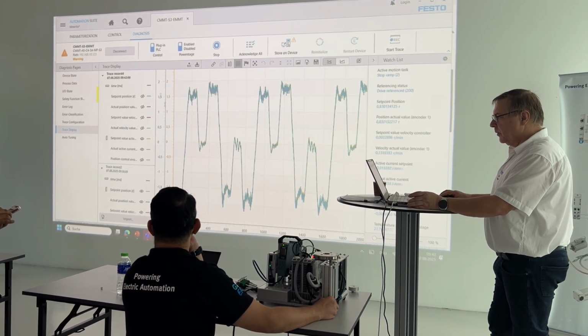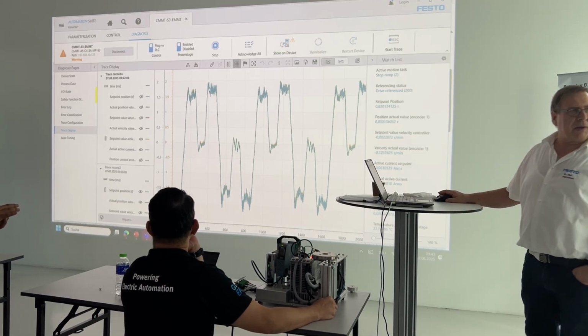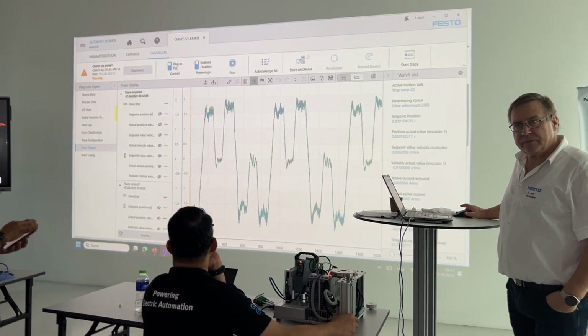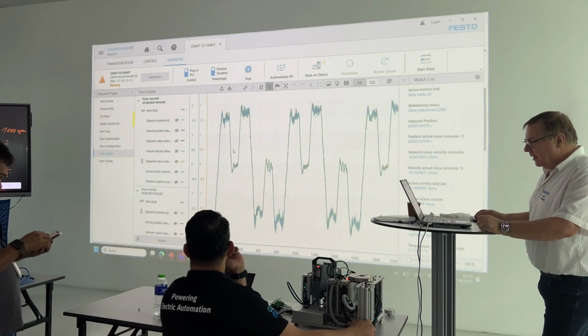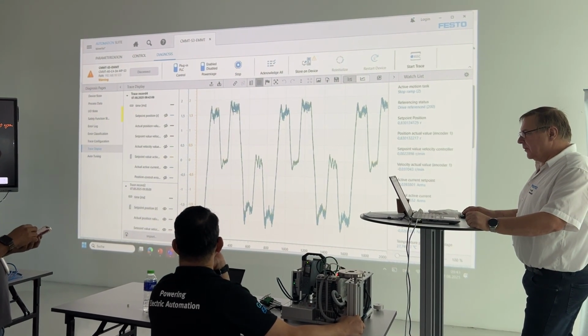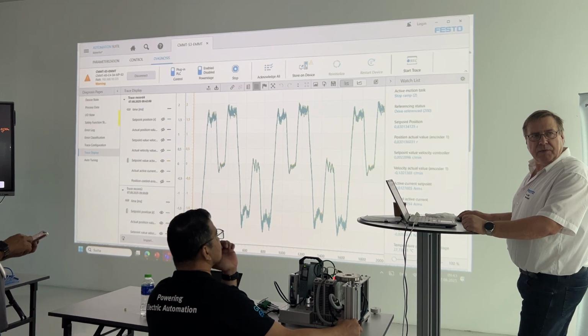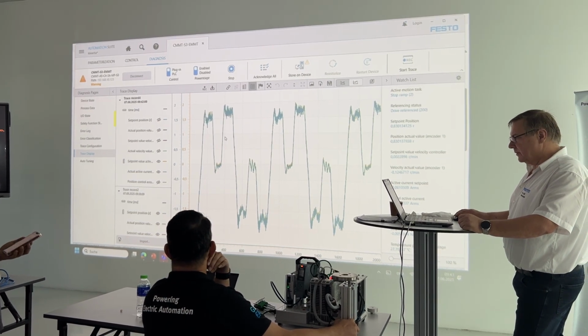Current, we are over the nominal one. We are in the overload range. But it's fine, because we have enough break time here. We do not have a big oscillation. This is only the standard one. Looks fine, so no self-oscillation was going.